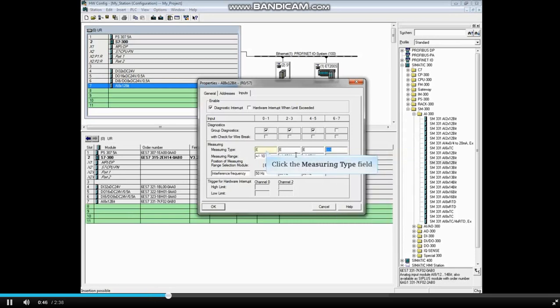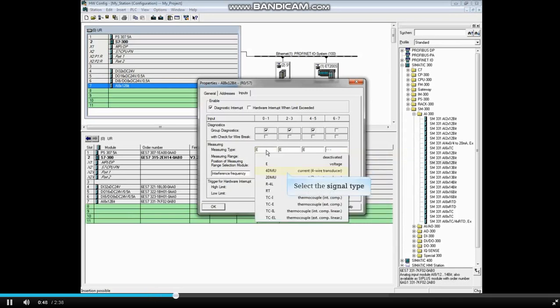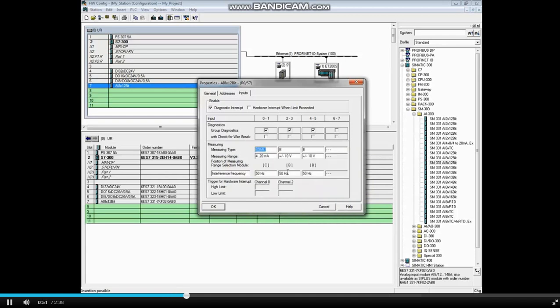Click the Measuring Type field to select the input signal for this channel group. The default measuring range is 4 to 20 milliamps, which is what we want.